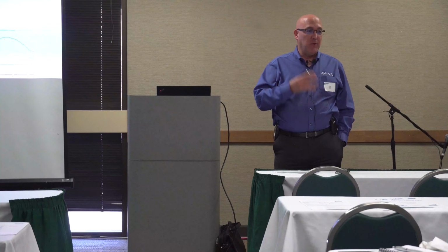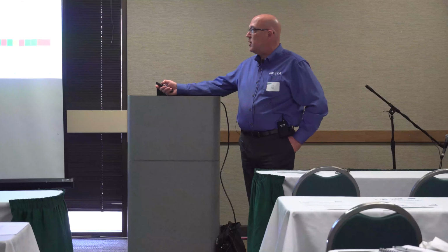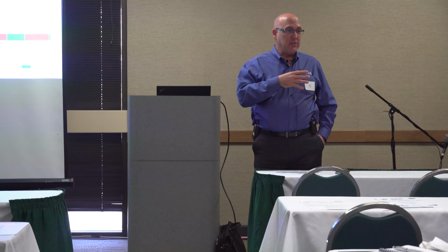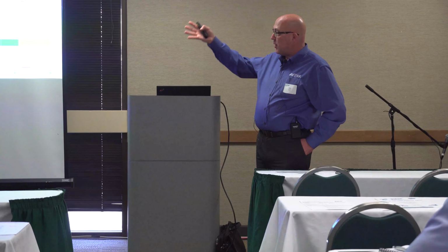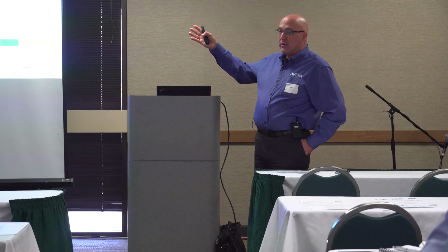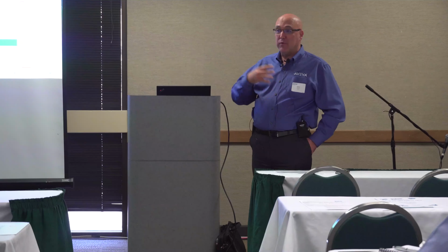It's got OEE, and there's mapping capability in the historian. So if you put geolocation on your tags, it'll lay them all out on a map if you want. If you've got multiple sites, it'll do all that. Here's OEE, the equipment utilization. So you have a tag here. You can do this manually or automatically based on the tags coming in. It'll categorize uptime, downtime, and reasons for doing things, build this whole sequence of time, and show all the status of your pieces of equipment. You can start the equipment, give it production rates, let it know how fast and how effectively it's making packaging or producing product or flow rate through a pipe, or whatever it is you've got. It'll calculate OEE for this thing.